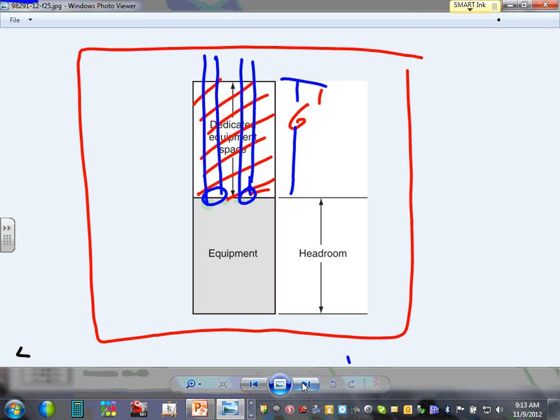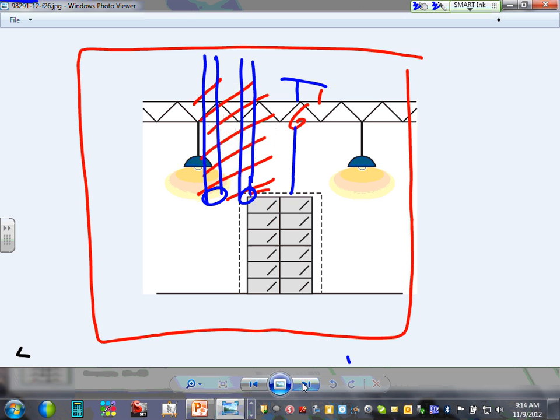So where's the dedicated space? Right here. Look at this panel right here. From here all the way to the pit, right from this top all the way 6 feet, or the structural ceiling, you can't put any pipe other than electrical. From here all the way down to the floor, you can't put anything other than electrical. Can I have thumbs up, Chad, to understand that? Okay. So that's basically your dedicated space.